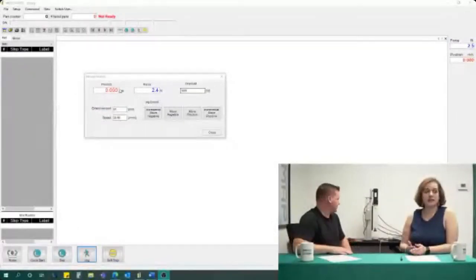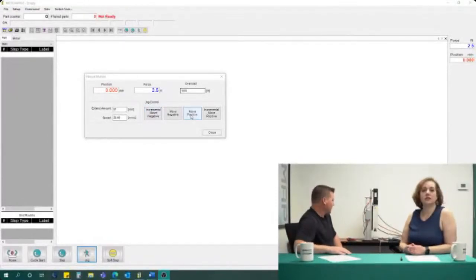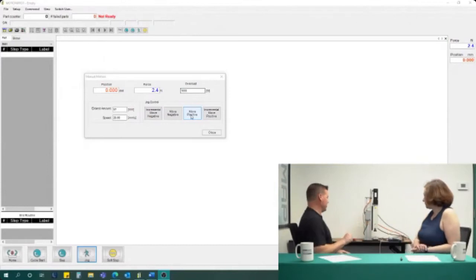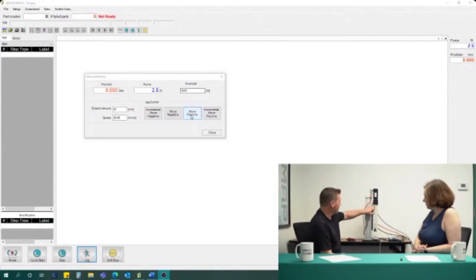One of the first things that we need to do is jog down onto our certified load cell. Before we do that, though, I would like to explain a couple of things that we have here. This is our 1 kilonewton press. This is our integrated load cell. This signal gets fed into our signal conditioner, which is where you make these changes manually. There are potentiometers in here that I mentioned before. We're going to adjust those so that it matches the certified calibration meter, where we have the load cell in line with the press. So like we just said, we're going to jog the press down.